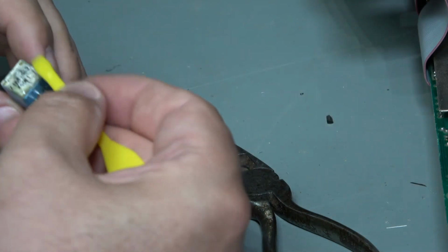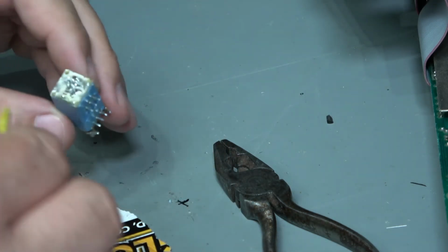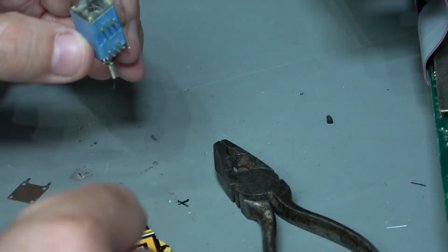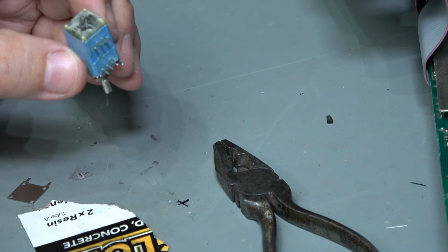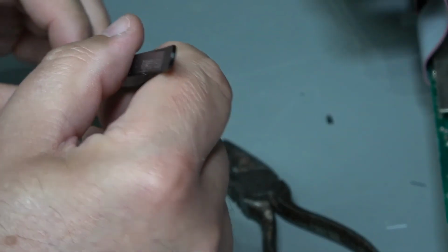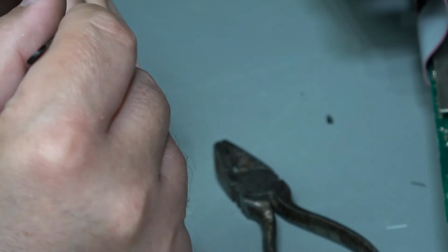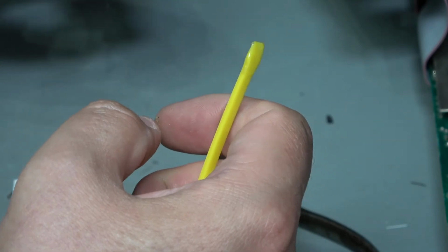Now, another method is I could have glued the 3 segments together, but then we would never have been able to do any repair in the future. Using this epoxy, it can always be scraped off and removed, if worse comes to worse. And I'm just going to use the tips on these slightly bent tweezers to make sure that I've introduced the epoxy fully into each of the tubes. Pushing it in there to make sure that we haven't just ended up with it on the surface. We should be there. Alright, let's just let it dry.